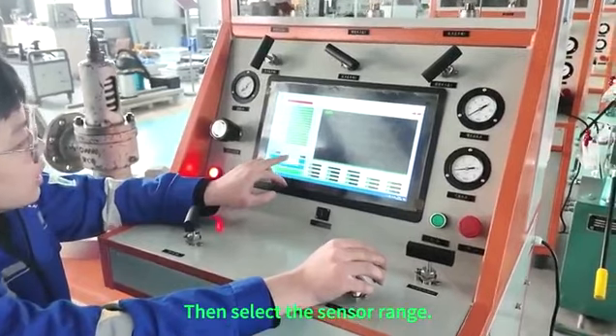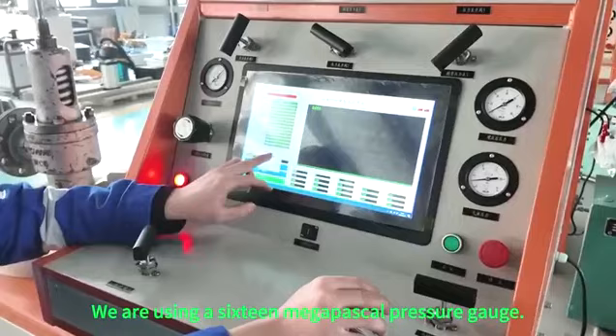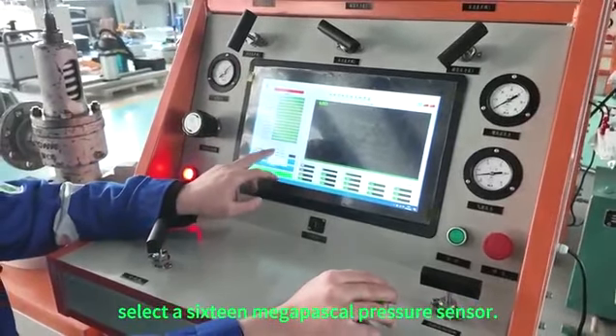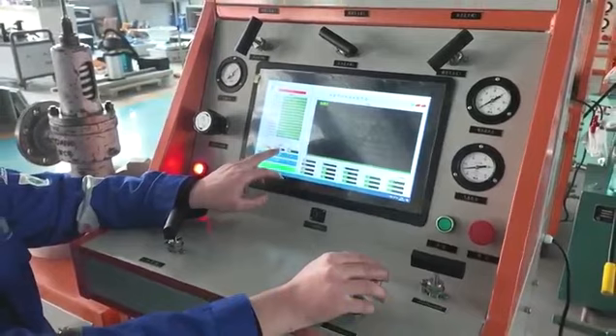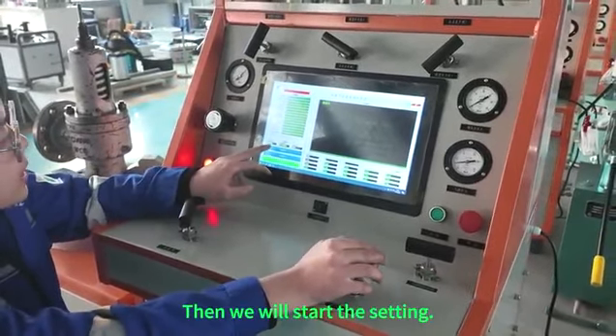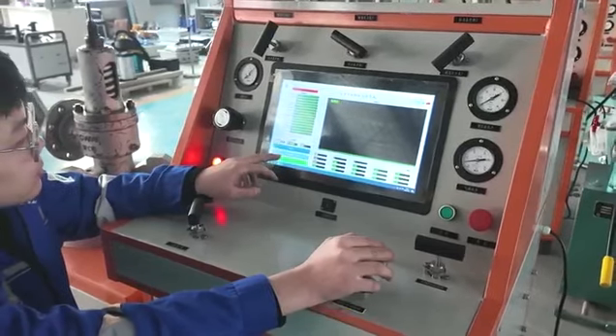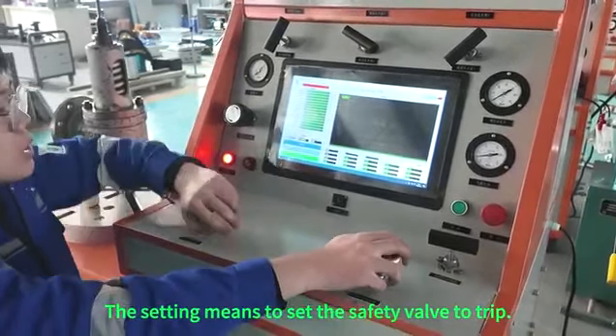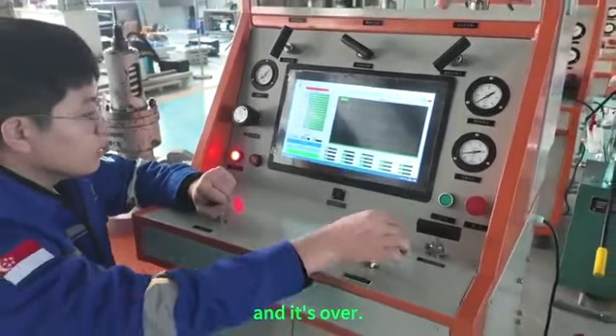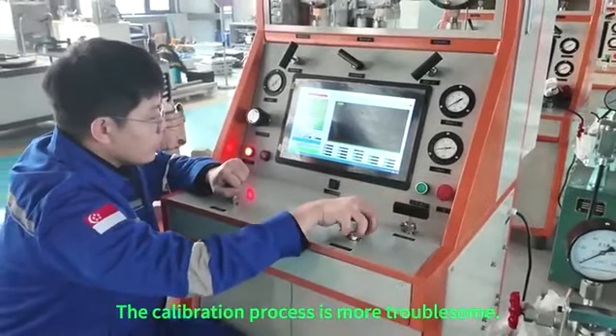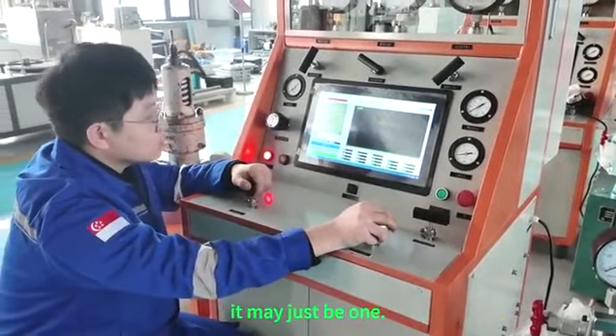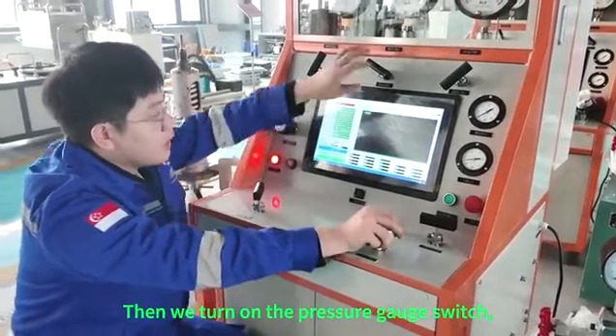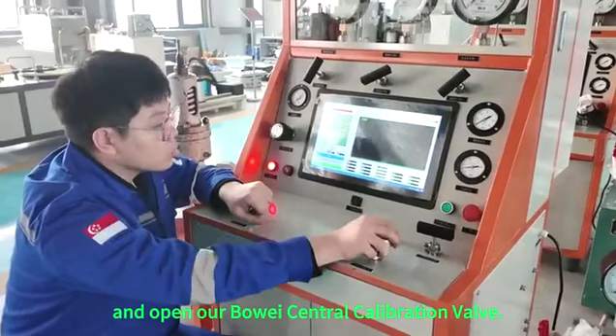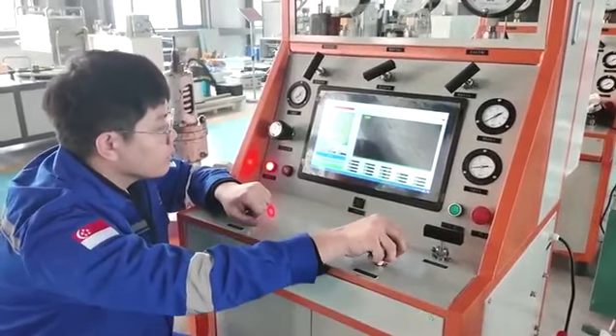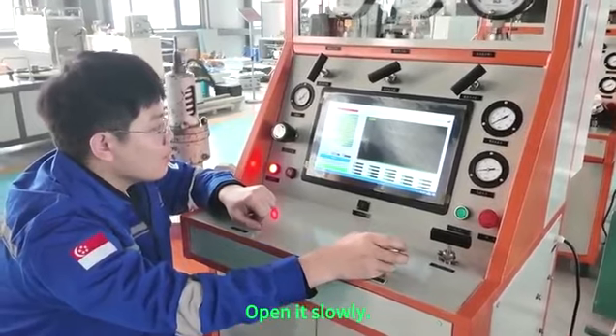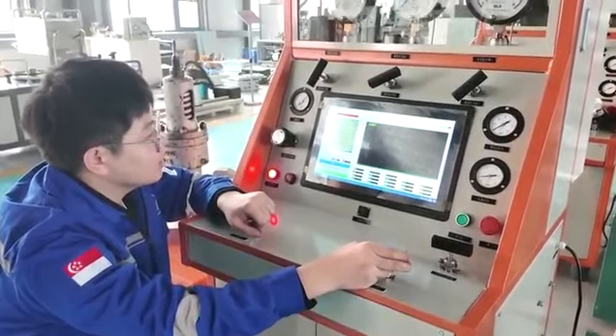Then select the sensor range. We are using a 16 megapascal pressure gauge, so select a 16 megapascal pressure sensor. Okay. Then we will start the setting. The setting means to make the safety valve trip. The calibration process is more troublesome. Then we turn on the pressure gauge switch and open our central calibration valve. Open it slowly, and don't open it too fast.